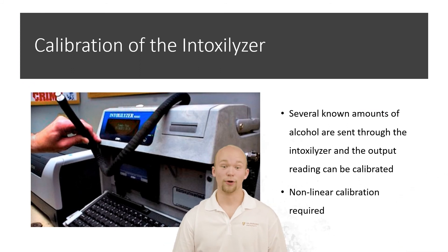Now let's take a look at the calibration of the Intoxilyzer. Several known amounts of alcohol are sent through the Intoxilyzer, and the output reading is then calibrated accordingly. This requires a multipoint or nonlinear calibration. For example, if a 0.05 blood alcohol content absorbs X units of IR energy, a 0.2 blood alcohol content would not necessarily absorb 4X units of IR energy — thus why we use a nonlinear calibration.